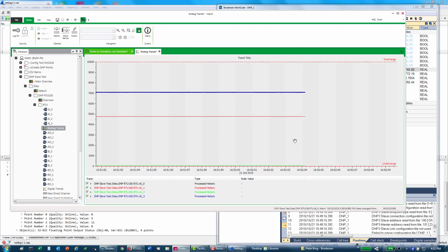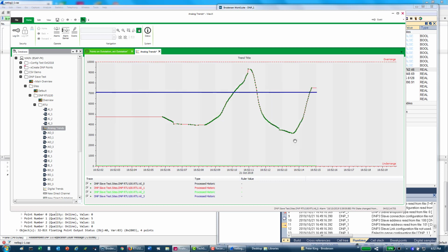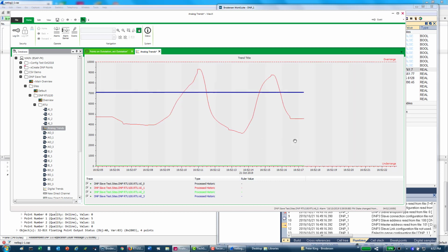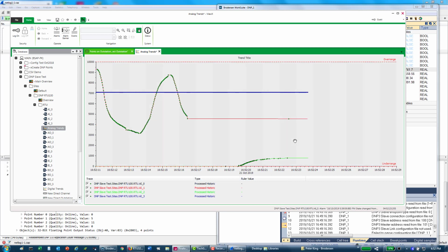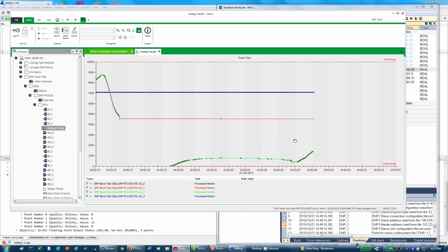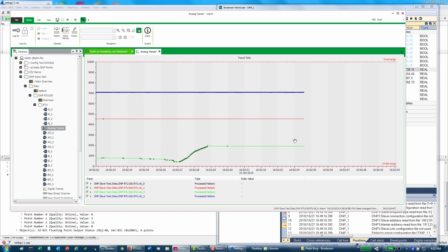So we'll just move it again, just a bit slower, but you can see how many events the RTU is creating. So as nice as my trends look, every one of those is being unsolicited as my Class 1 event. If I go to the next pot and do something similar, see there's a slight lag when I make a change. It's because we made this one a Class 2 event, and there has to be, I think it was 5 events before it gets unsolicited.